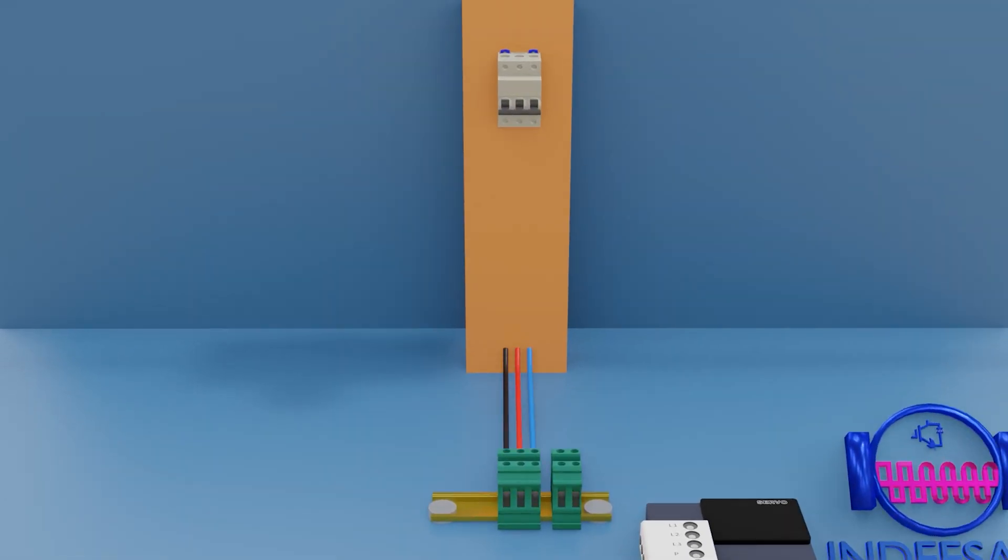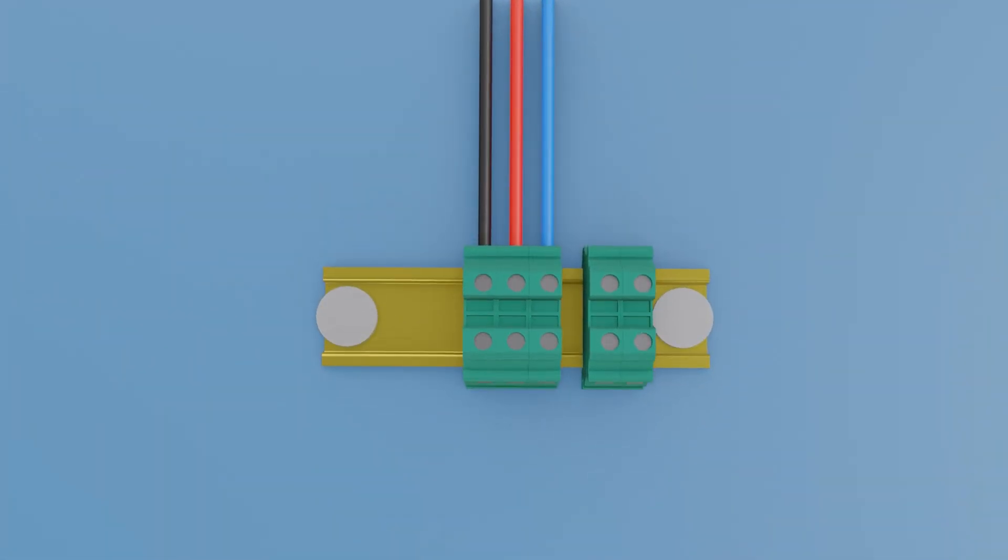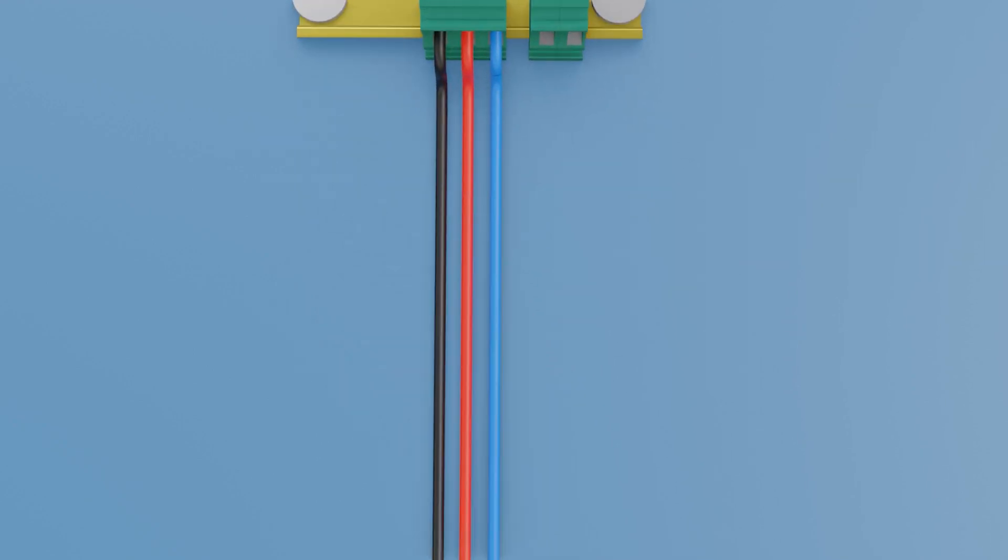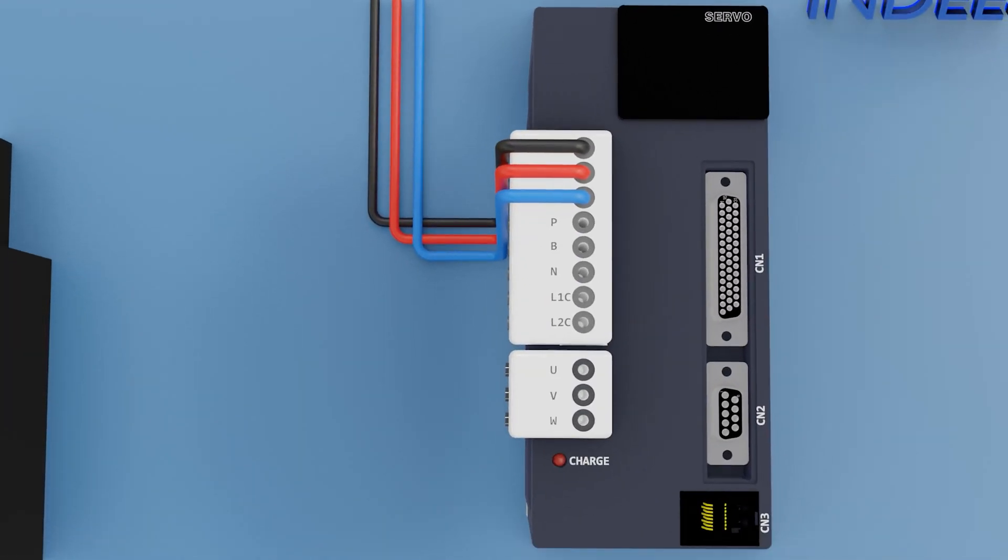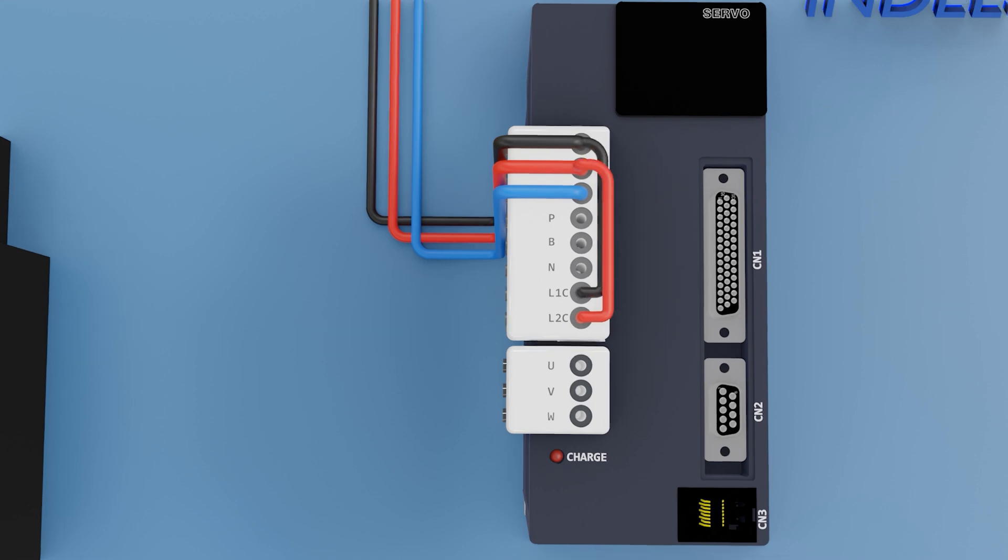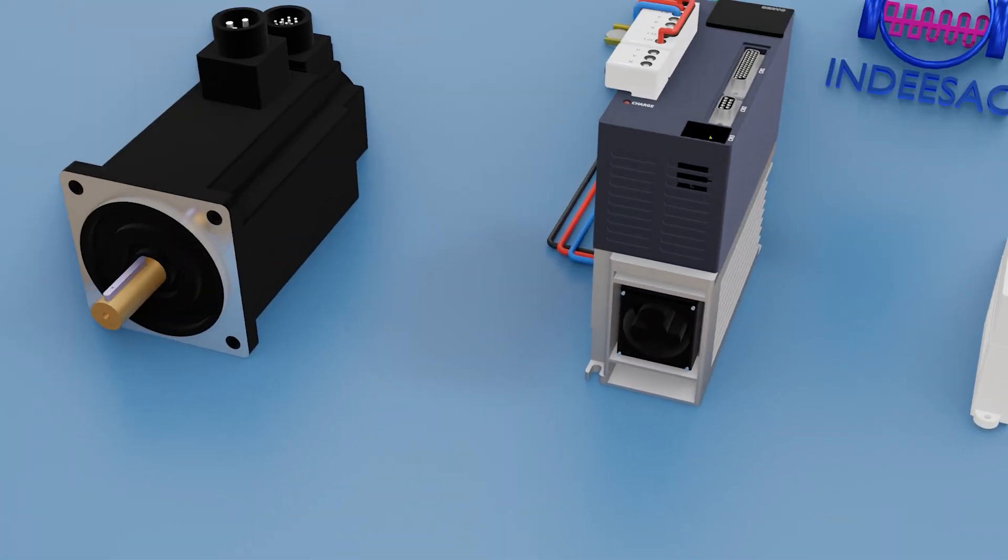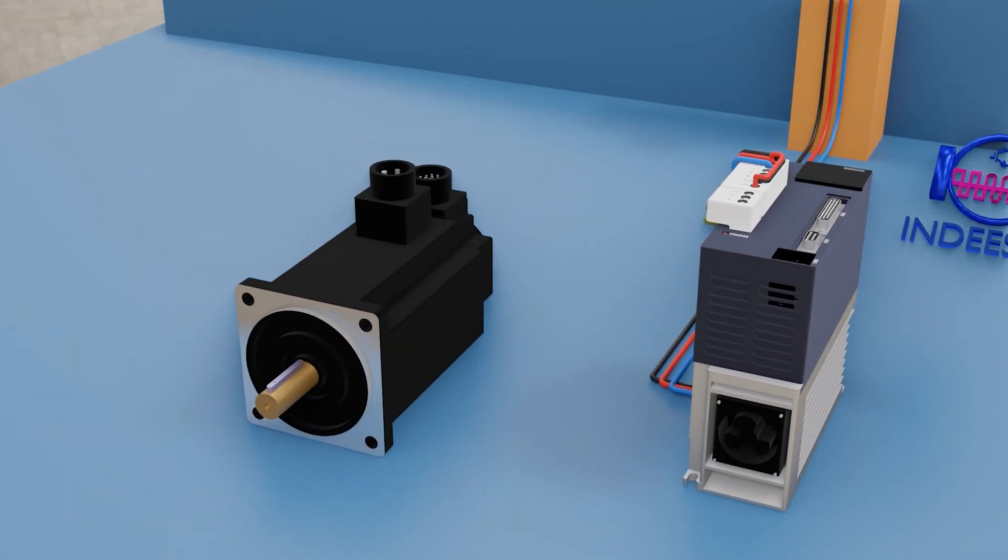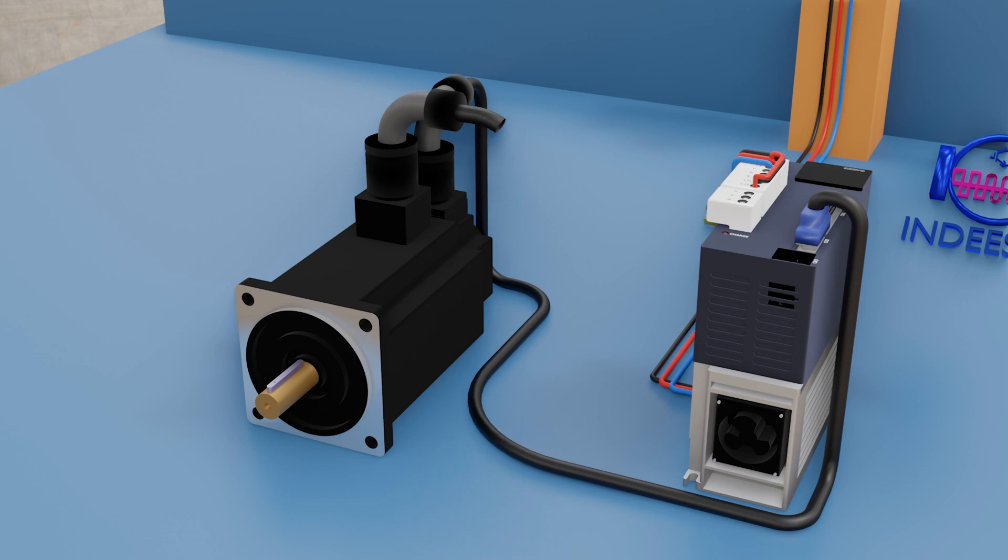Now it is necessary to connect the L1C and L2C respectively with the L1 and L2 to activate the control circuit of the input terminal, that is the CN1. Then we connect the servo motor, first the encoder cable that goes to CN2, and then the connection terminals.